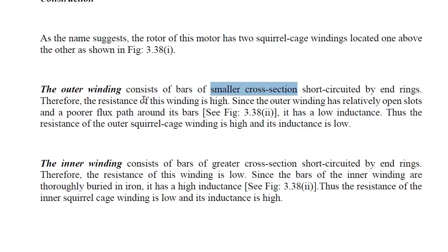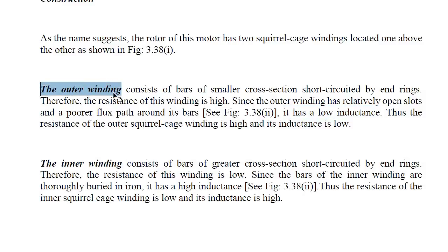Since the outer winding has relatively open slots and a poorer flux path around its bars, it has low inductance. The outer cage bars are placed in open slots, which results in a poor flux path and therefore low inductance. So the outer winding has high resistance and low inductance.